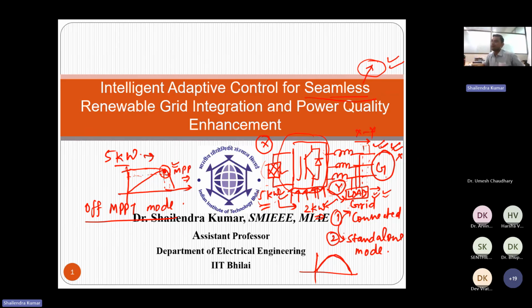So we can operate in off MPPT mode, and the generation itself is reduced to match the load demand. Not only can we reduce to 3 kilowatt or 2 kilowatt, any load power. Certainly, after some time, if the load is reduced to 1 kilowatt, it will supply only 1 kilowatt power.